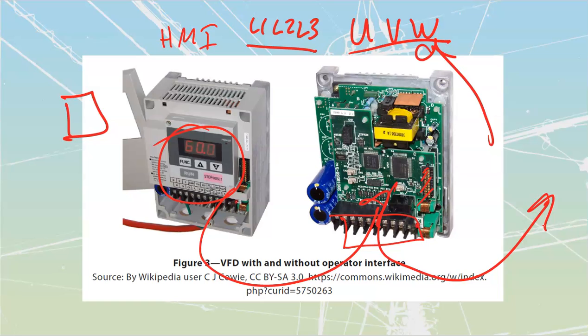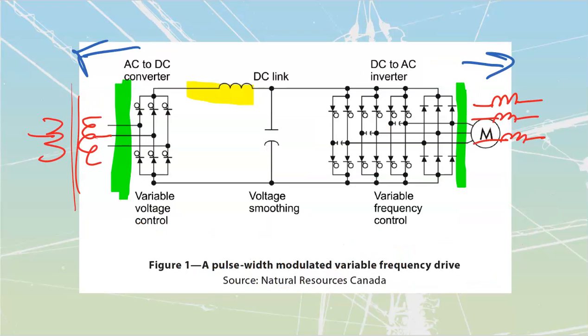The motor, we've talked about a number of times as well, needs to be inverter duty. This is the first place that the module even bothers to explain what that inverter duty is. Inverter duty is just a motor that has hardened windings and better quality insulation. It's able to withstand the reflected waveform. It is going to have slightly larger conductors inside of it per horsepower, because we have more skin effect inside of those as well.